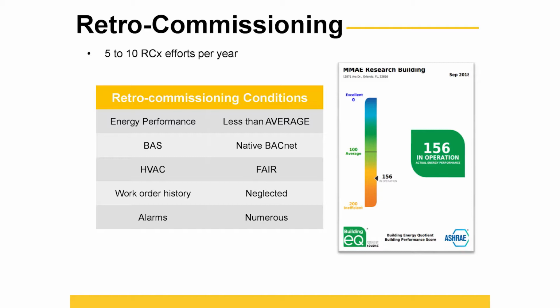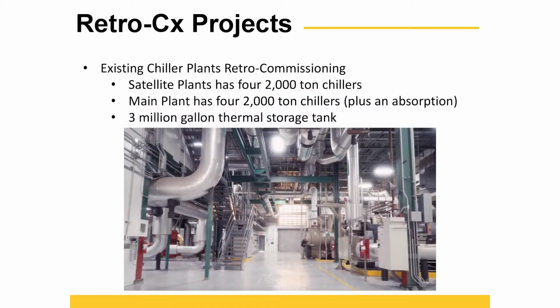So these are really the checklists: is the energy performance less than average? I have a native BACnet system, and my systems are still within their life cycle as far as mechanical is concerned, but our work order history and BAS alarms indicate that entropy is preying on this particular building. That makes it a perfect candidate for retro-commissioning.